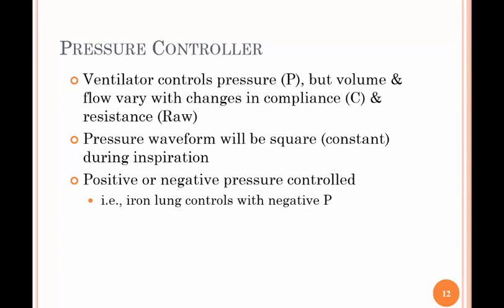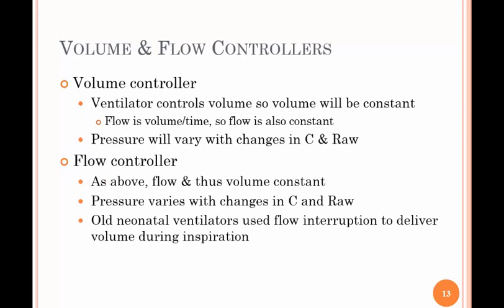The pressure waveform will be square, or referred to as a constant waveform, during inspiration. Positive or negative pressure is controlled — in essence, the iron lung controls the negative pressure. The volume controller means the ventilator controls the volume, so volume will be constant. And since flow is volume over time, flow is also constant. Pressure will vary with changes in compliance and resistance.